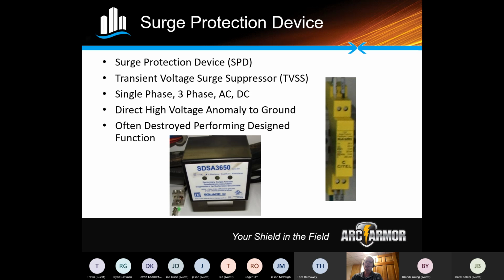I'll just throw out there, there are basically several types of surge protection devices, and they all have their form, fit, and function. Type 1 is primarily to protect incoming power on 3-phase or 120. It's usually upstream of the breaker. So if you have a main breaker in your building or in your panel, those are designed to be upstream of that. Type 2 is designed to be downstream of a main breaker. It does the same function as a type 1, but it's on the load side.